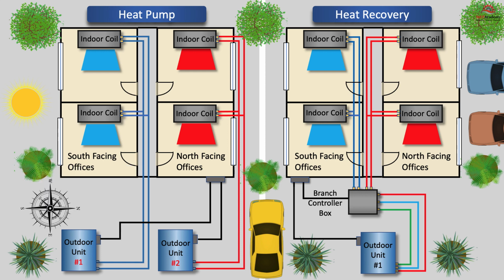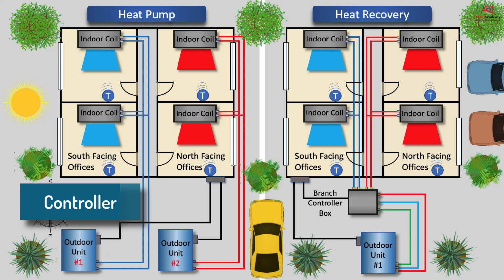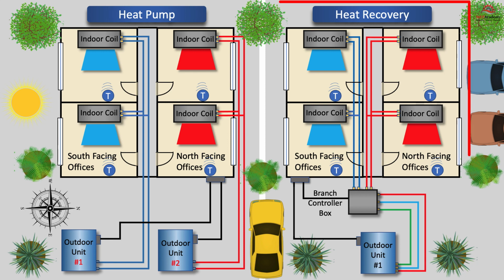All of the indoor fan coils will have their own controller, so there is no difference in cost between the 2 systems here. The VRF heat recovery system will most likely require the greatest initial investment when compared to VRF heat pump or traditional air conditioning systems. The additional cost for the VRF heat recovery system comes from having more components and a higher level of installation and commissioning costs. The initial cost of a VRF system should be analyzed based on life cycle cost, which will be impacted by the energy cost and saving factors.